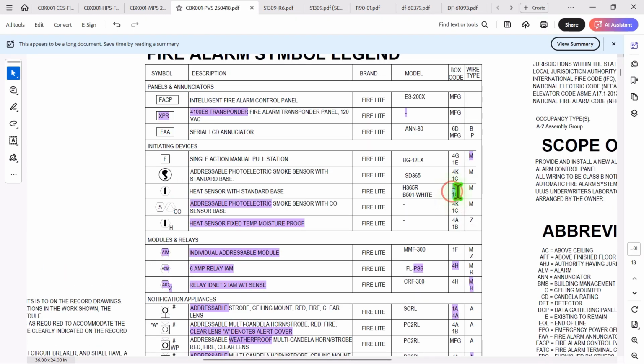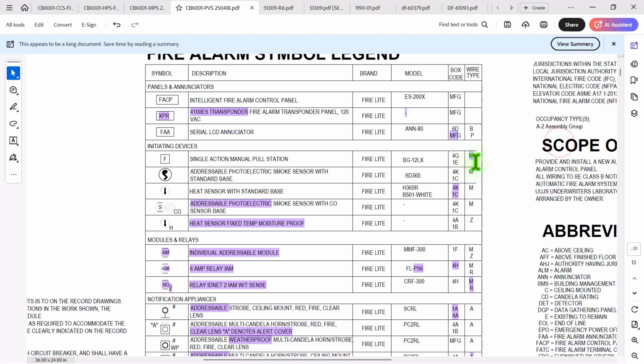The smokes and the heat, we have to add a 4-inch round electrical box for the smoke and heat. The remote annunciator is going to be 4G, so that should take care of all of that. The pull station is going to be 1F with a flat mud ring - that'll be for the pull stations only.